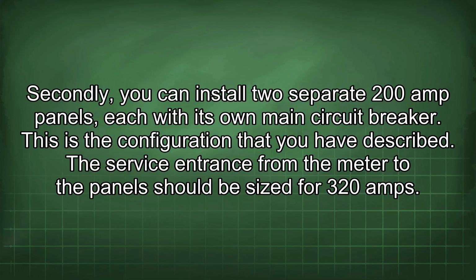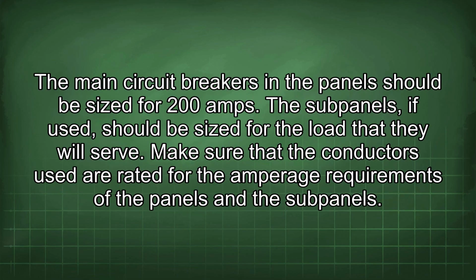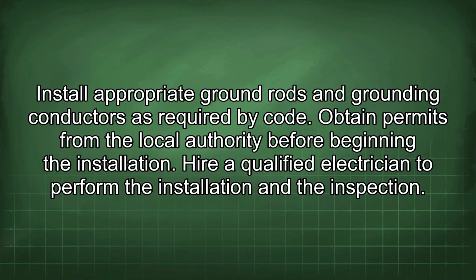The service entrance from the meter to the panel should be sized for 320 amps. The main circuit breakers in the panel should be sized for 200 amps. The subpanels, if used, should be sized for the load that they will serve. Make sure that the conductors used are rated for the amperage requirements of the panels and the subpanels. Install appropriate ground rods and grounding conductors as required by code.